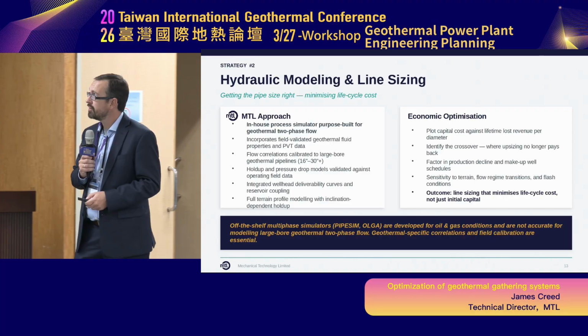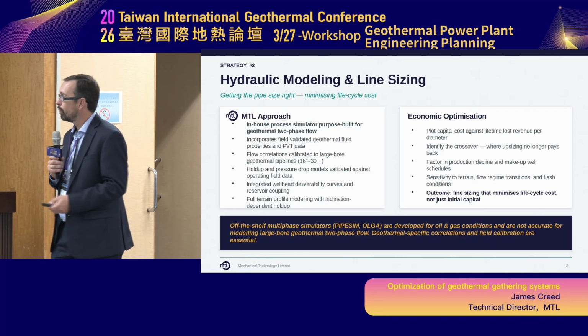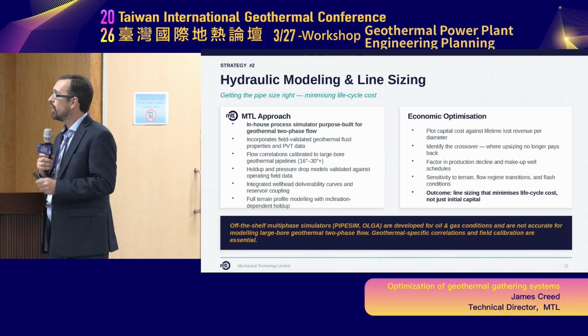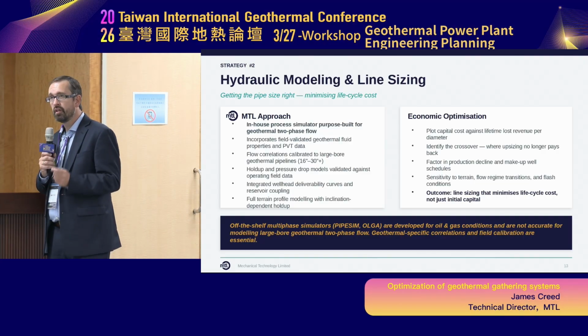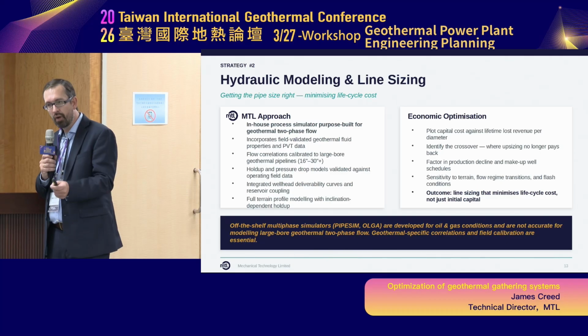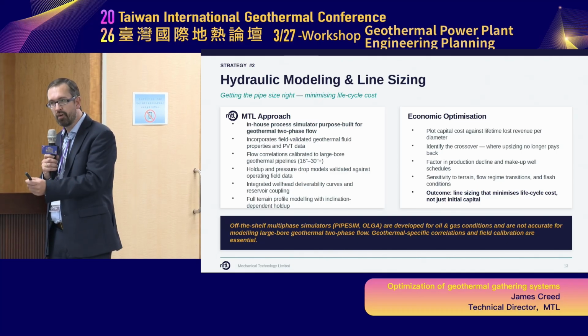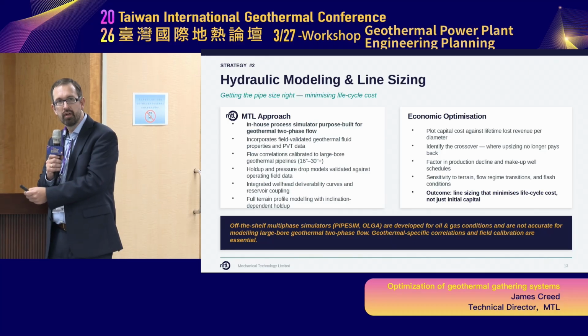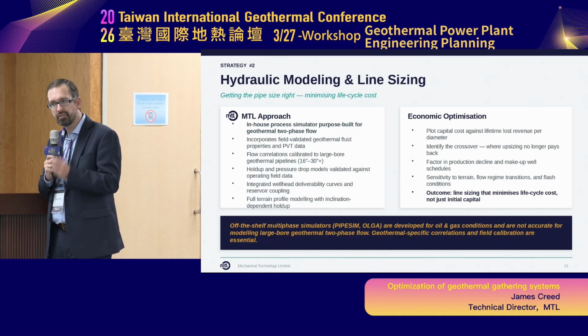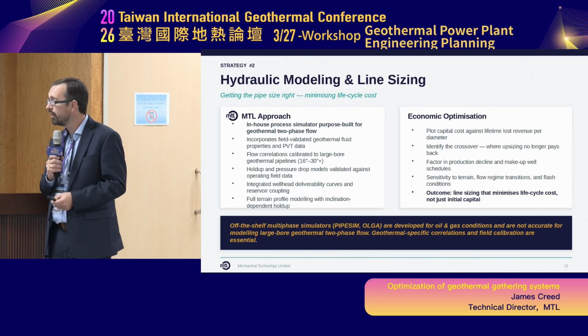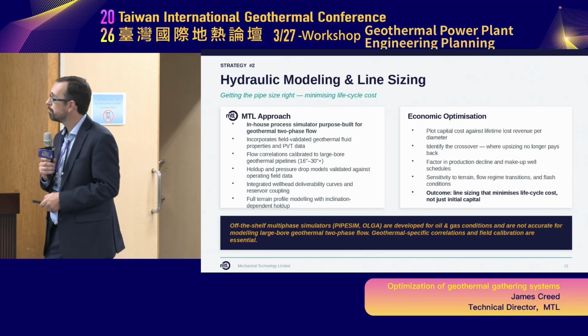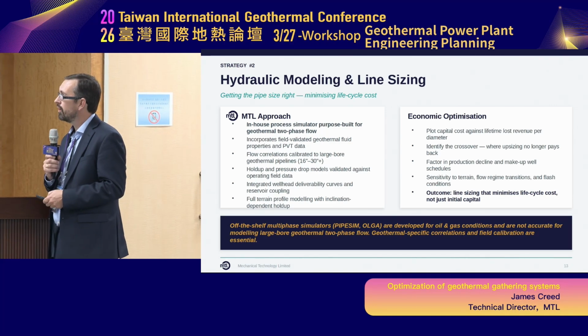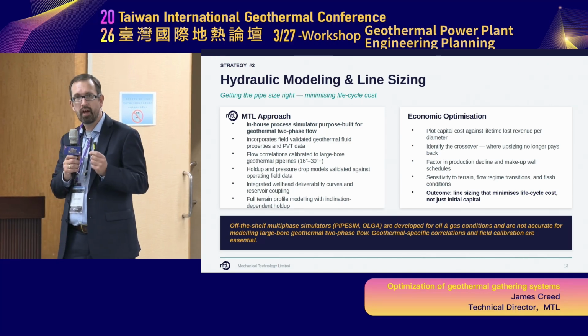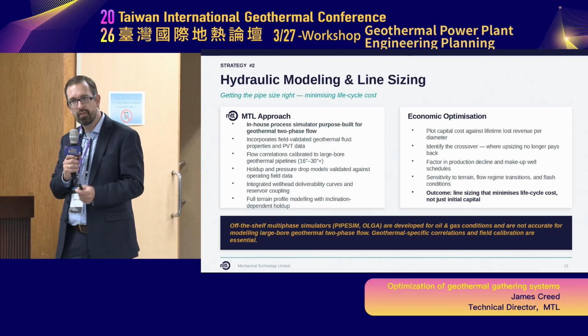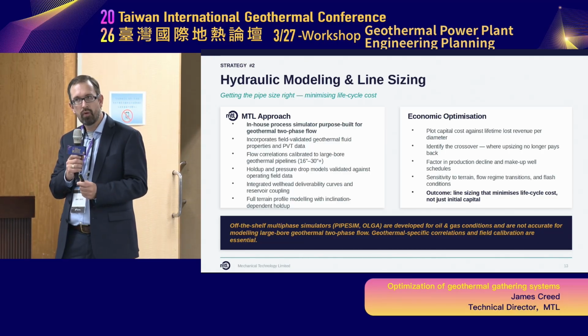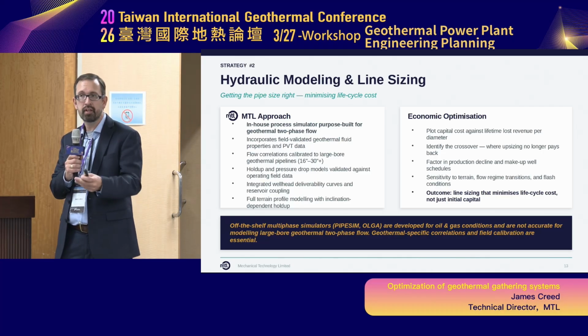So, hydraulic modelling and line sizing. One key point is you have to look at your pipe sizing to make sure you're designing it both for day 1 operation, but also for year 5 and year 10 operation. If you don't get it right at the start, you'll see a second round of capital cost later on. Our point here is you need a good understanding of how to do pressure drop calculations and what variables to consider, and that comes down, from our perspective, to experience.